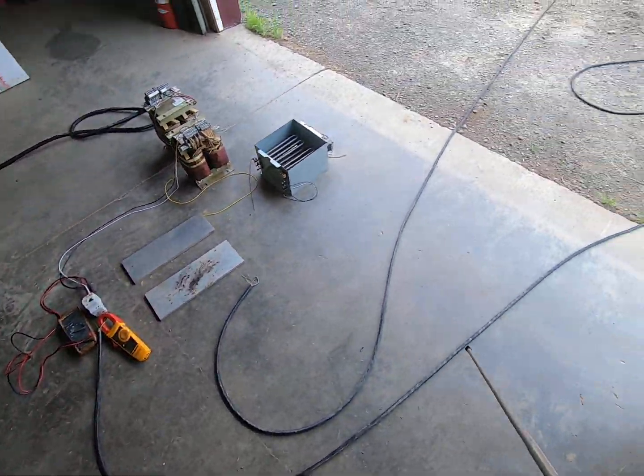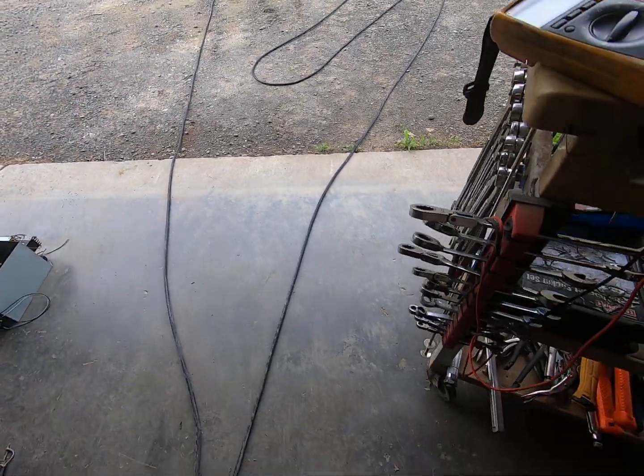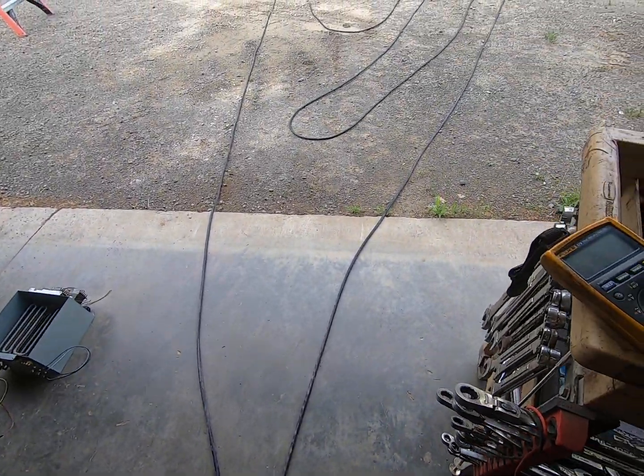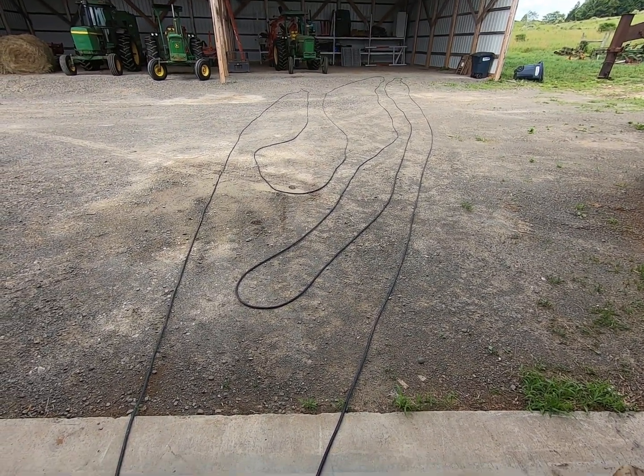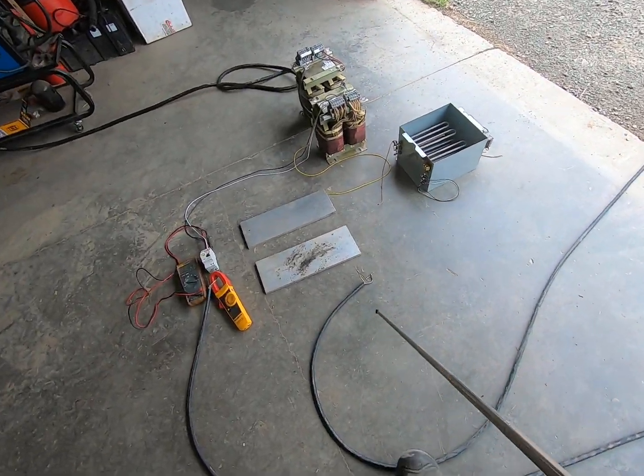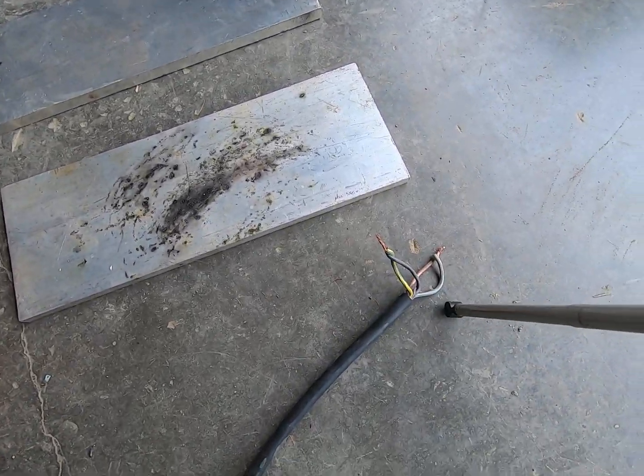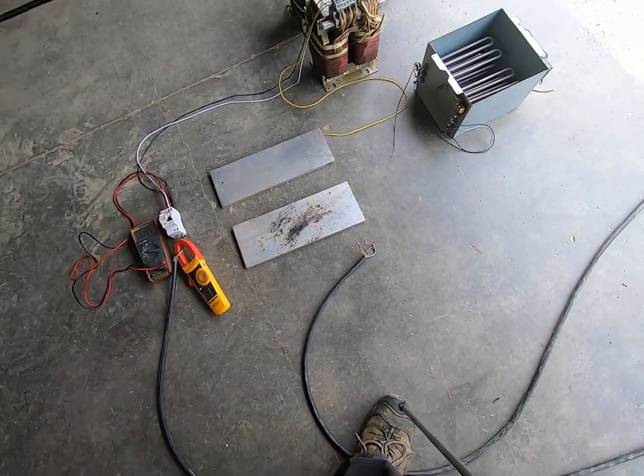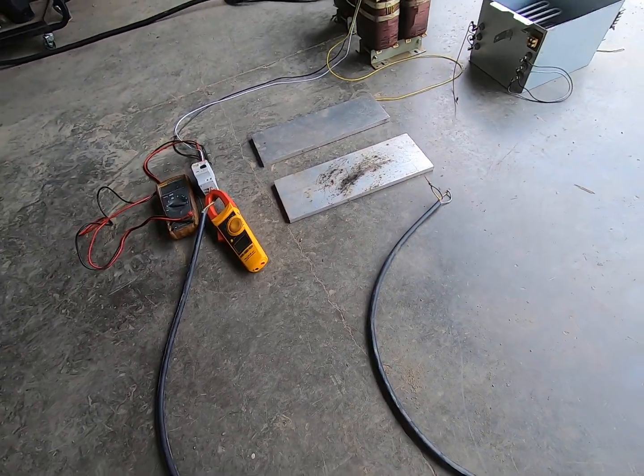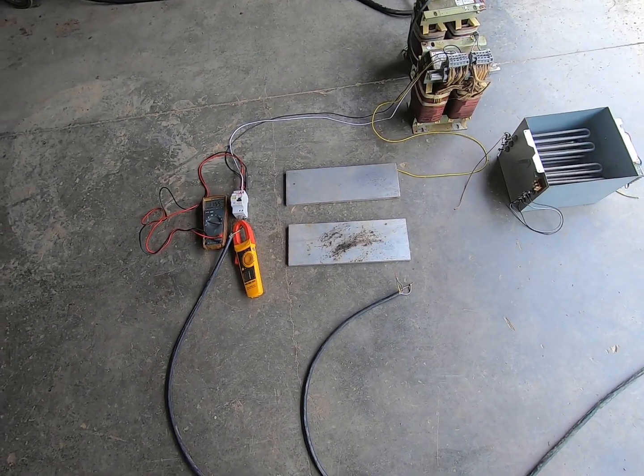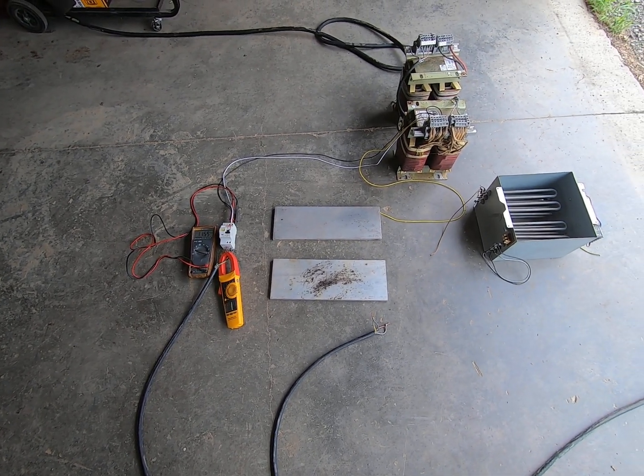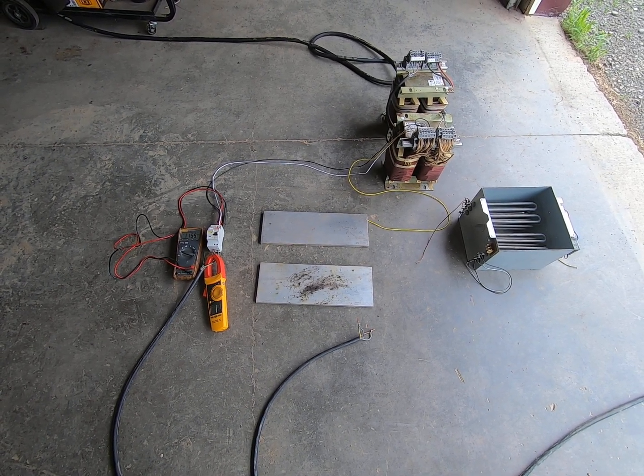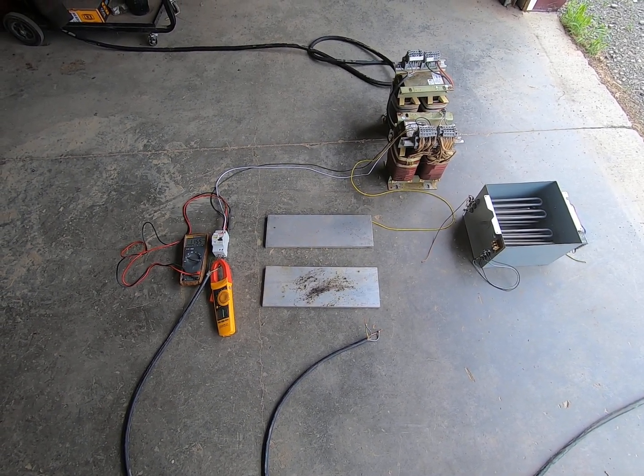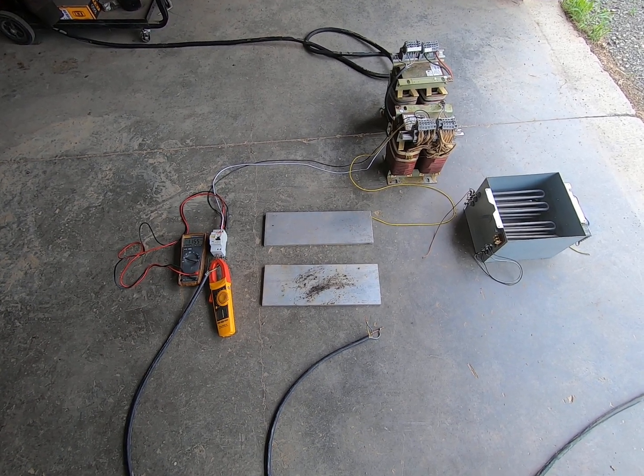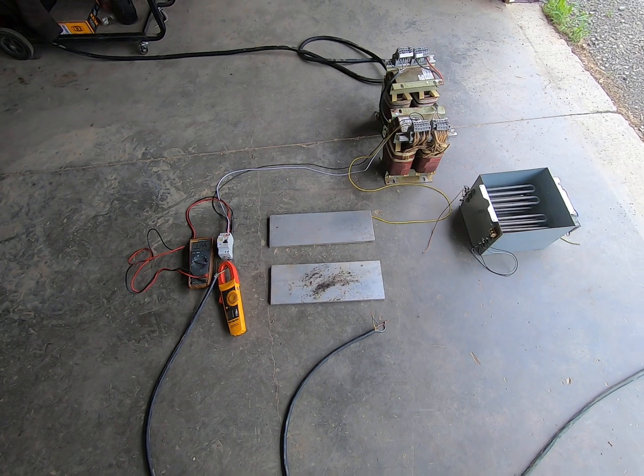The cable I have is 1.5 millimeter cross section, and I have 93 meters of it, and then it comes back in, and I have the two ends shorted together, so the conductors are paralleled, effectively making a 3 millimeter cross section for the wire size. The turbine itself actually has a 2.5 millimeter cross section, which is roughly a 14 gauge wire. These parallel together gives me roughly a 13 gauge wire.